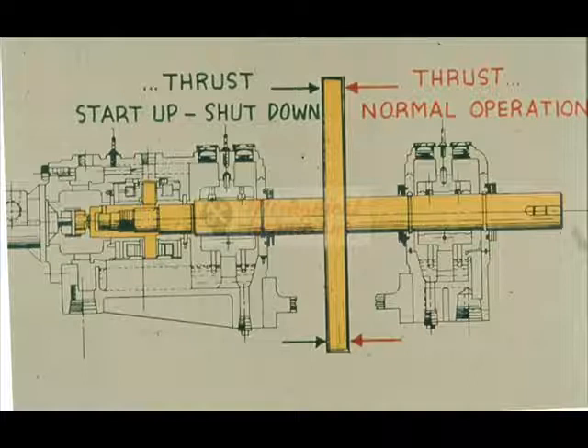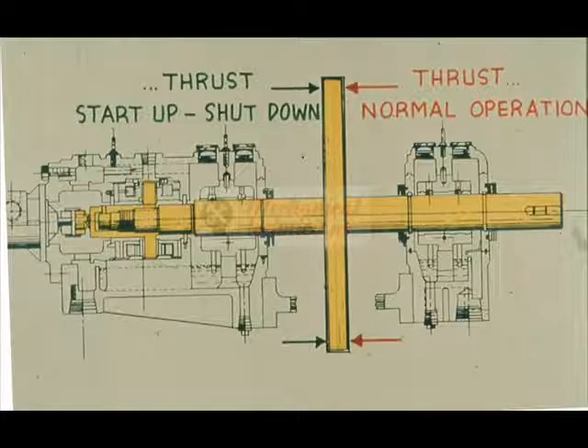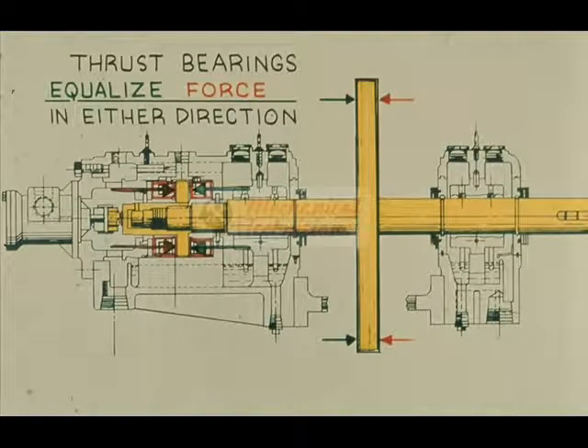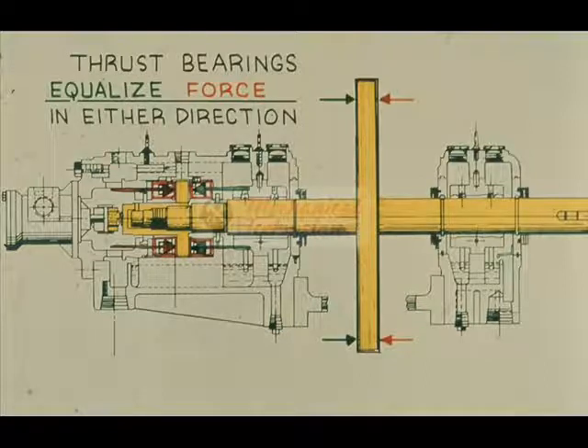Bearing thrust loads cannot exist in opposite directions at the same time, but we frequently find thrust appearing in one direction during normal operation of a machine, with the thrust changing direction during start-up and shut-down. Thrust bearings of the type we will be discussing must therefore be capable of equalizing thrust loads in either direction.